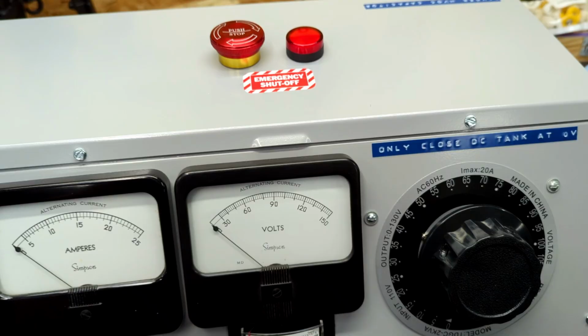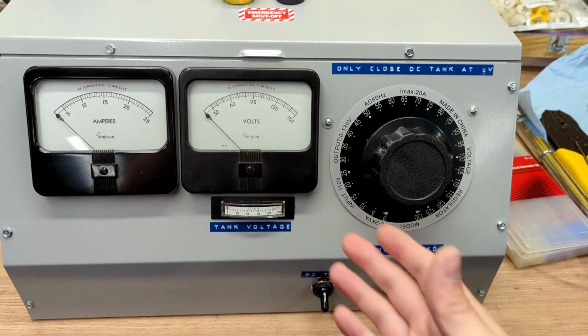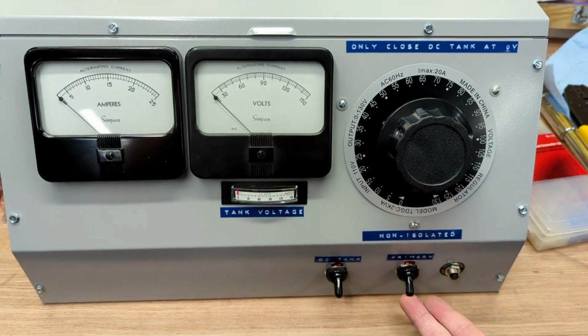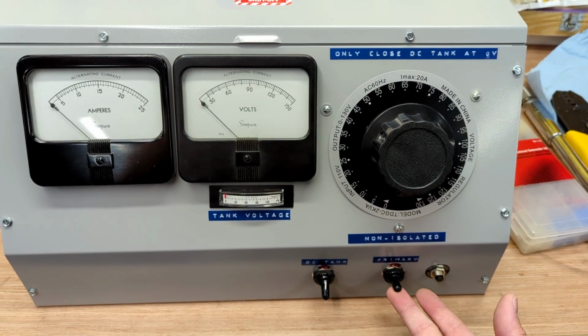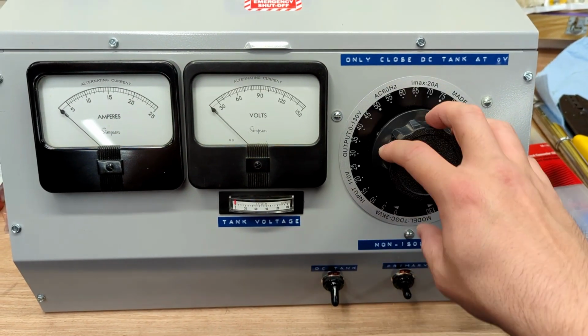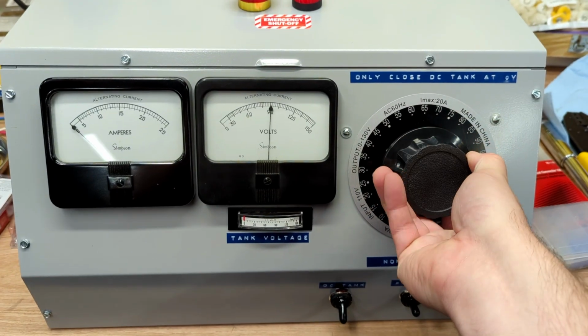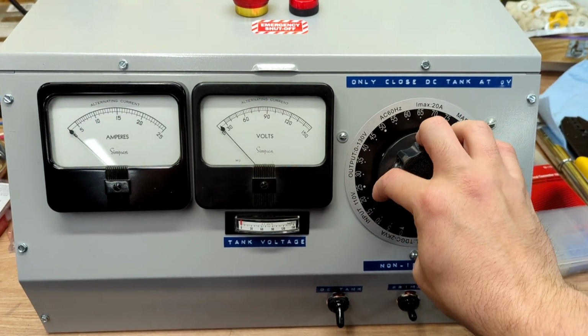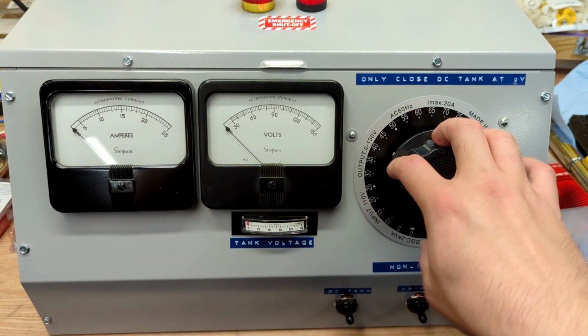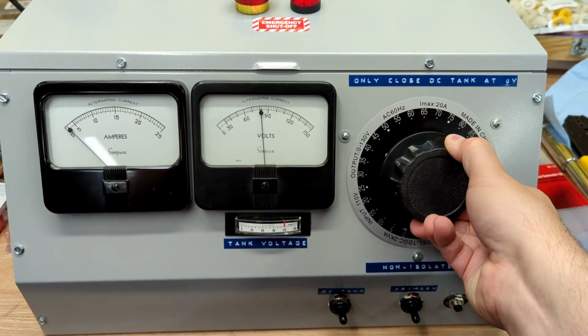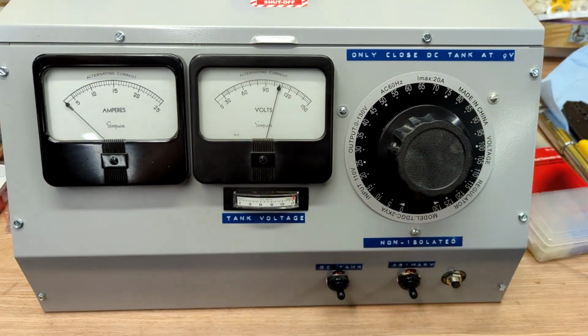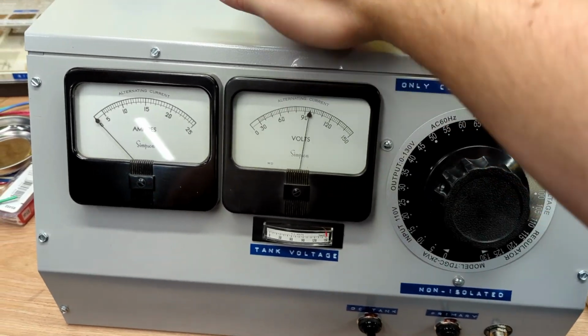That powers it up. Nothing has been done yet, because in series with the e-stop circuit, I have to close this. I just heard the main relay click, so I've got power, the AC side is working. Watch, I'm going to turn on the DC tank, and we'll charge this thing up. Watch the tank voltage, put some current in this thing here, get up to 150 volts, and I'm going to slam e-stop.